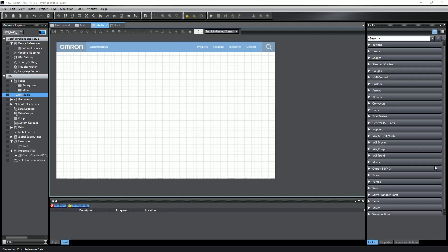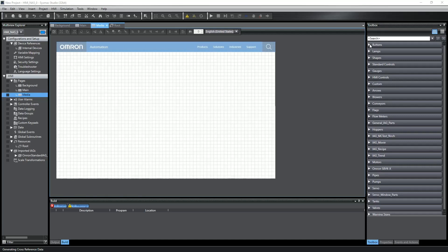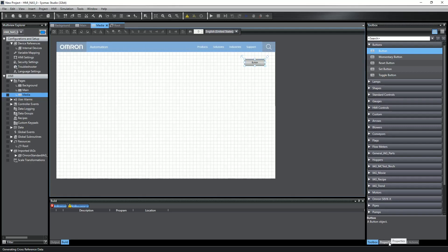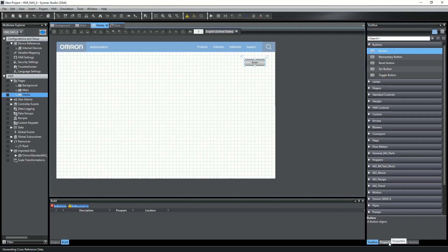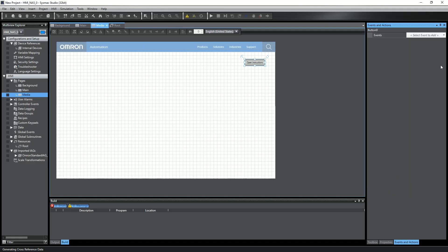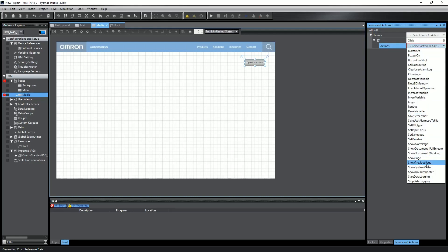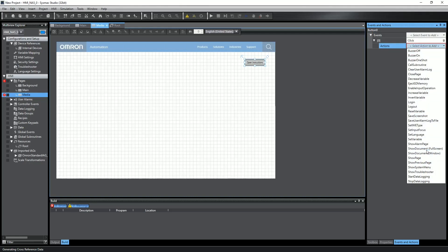Loading these files into your HMI project takes just a few clicks. First, let's start with a PDF file. On an HMI page, I'll add a button onto the page and then edit the text to make its purpose clear. Now with the button selected, I click on Events and Actions, add an event for when the button is clicked, select Show Document, and then I just need to select the document I want to have open.